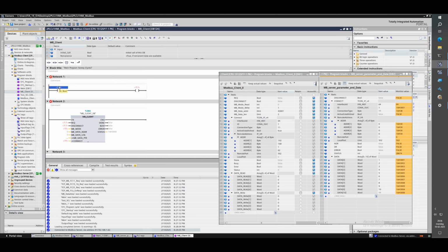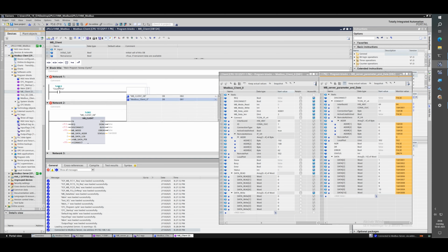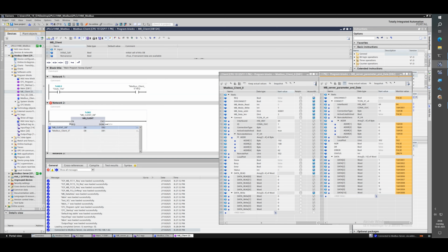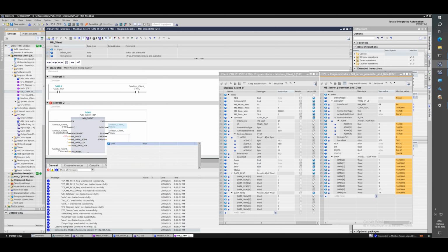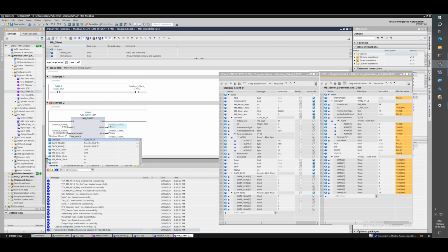We need to request data when we're using this client because we will block the communication path. Therefore, I'm using a system bit for 1 Hz and sending that to the Modbus request. You can see that here. And now I'm beginning to set up some of the values. I'm not setting up all of them because some of them I can also just write. Specifically, the addresses can help depending on your application. Connection is, as you can see, from the database, and basically just setting everything up so we have all the data in one place instead of looking at the ladder programming. I find it easier to set with compared to blocks where I have all the data live in my from my databases.